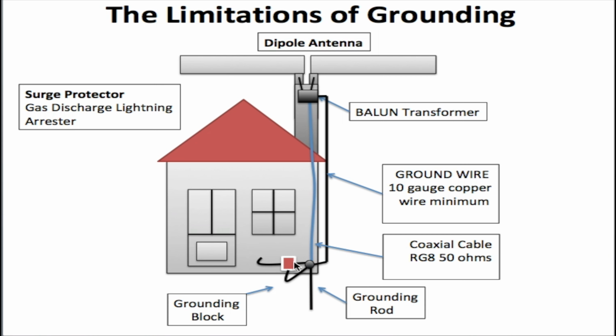So once it gets to that point, what happens is that there's a glass tube in the surge protector and it has a gas within the tube. When there's a surge of voltage, this gas changes to a plasma and it forms an arc right to ground. It's like a wire being formed and goes directly to ground, and it leads that high voltage to ground. So that high voltage will go right to ground and it will be dissipated. And that way you avoid it going right through to your equipment. So this is how it does it.